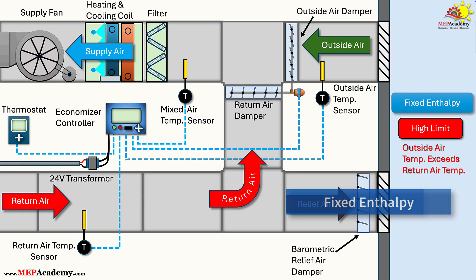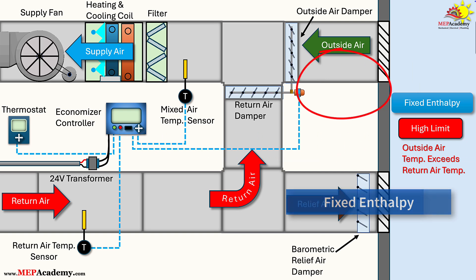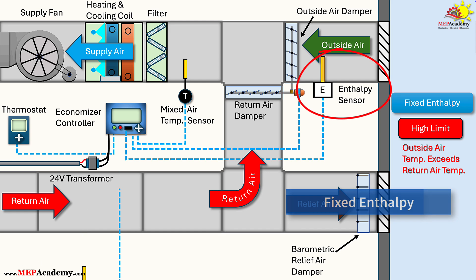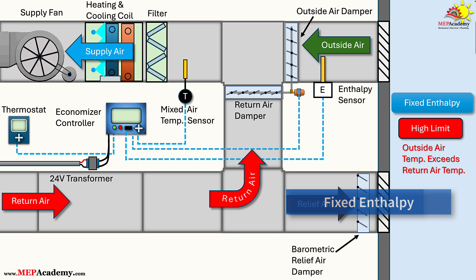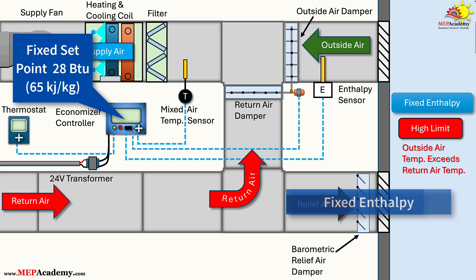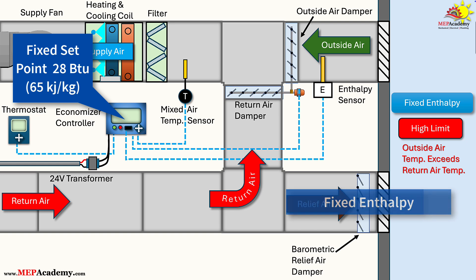Fixed Enthalpy Strategy. The first thing we'll need to do is swap out the dry bulb temperature sensor with a combination dry bulb temperature and humidity sensor. The fixed enthalpy strategy accounts for both temperature and humidity by measuring the outdoor air's enthalpy – total heat content – and comparing it to a fixed enthalpy set point, typically around 28 BTU/lb (65 kJ/kg), which corresponds to conditions like 75°F at 50% relative humidity. If outdoor enthalpy exceeds this value, the economizer disables. This requires enthalpy sensors or a combination of temperature and humidity sensors to calculate enthalpy.